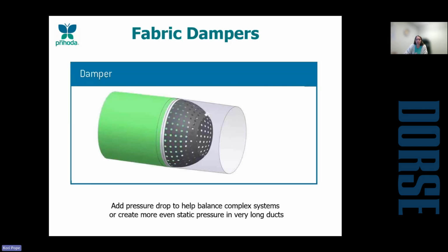We also have an adjustable version. This is what we call the damper. So this just provides more flexibility once it arrives on site for balancing and correcting any type of turbulence and pressure issues. So the damper can be located anywhere downstream of the inlet. So like any elbows or T's on the system, we can put those there to help prevent any type of issues.